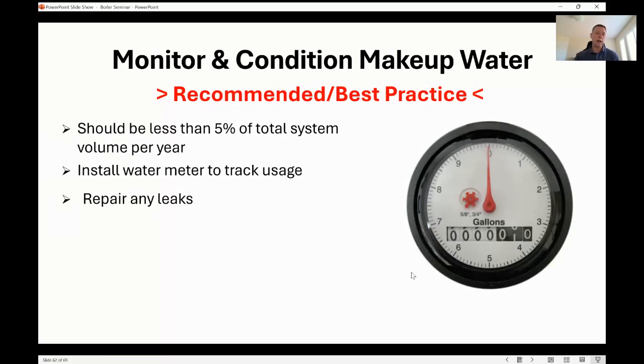You don't know. If you find that you should have less than 5% of your total system volume per year in makeup water. If you have more than that, something's leaking. If it's untreated, you have more scale coming into your hydronic system that's going to precipitate out. And always repair your leaks.